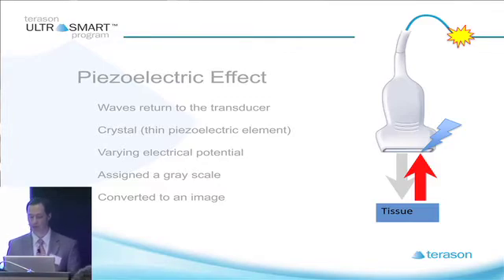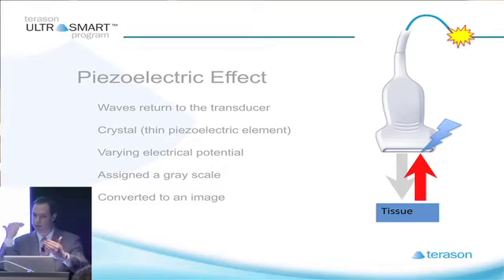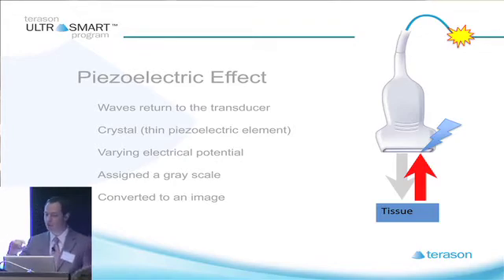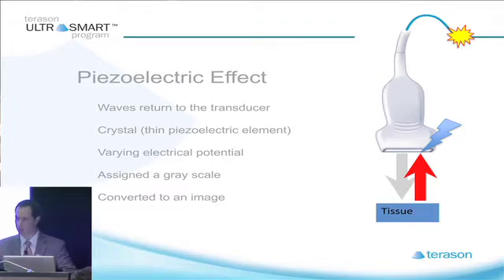That signal goes down to the tissue, then bounces off structures within the tissue, and comes back up toward the transducer. The same piezoelectric element that sent out the signals is now receiving them. It generates a varying electric potential depending on the strength of the returning signal, which is assigned a grayscale value and converted to an image.